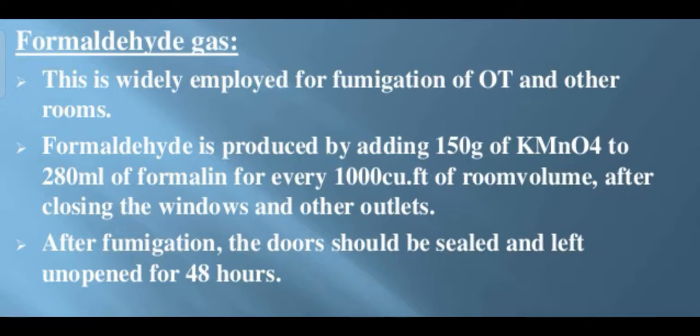Formaldehyde sterilization is used where sterilization by steam or high temperature is not possible. Typical equipment suitable for low temperature steam formaldehyde processing are rigid or flexible endoscopes, all heat sensitive instruments for advanced eye surgery like cryo instruments, plastic materials such as syringes, coils, or tubing. It is considered even more dangerous than ethylene oxide and is therefore less commonly used for sterilization.